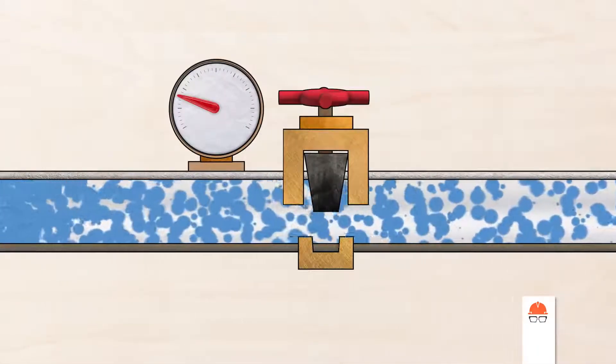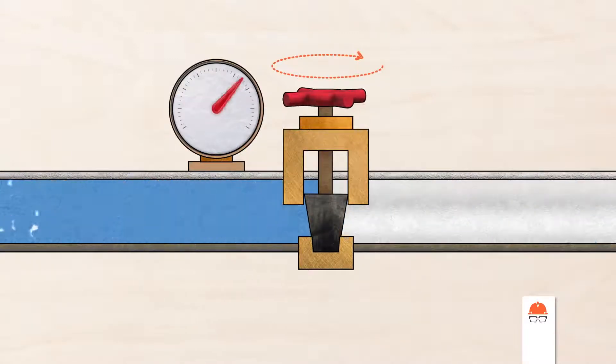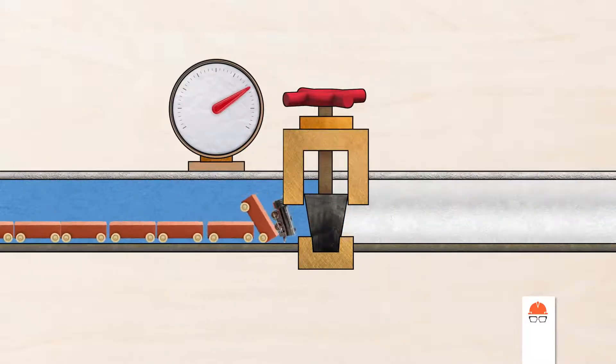Imagine you're an operator at the end of this pipeline in charge of closing a valve. If you close it quickly, you've essentially slammed those trains into a brick wall, and the pressure spike that results from such a sudden change in momentum can rupture the pipe or cause serious damage to other parts of the system.